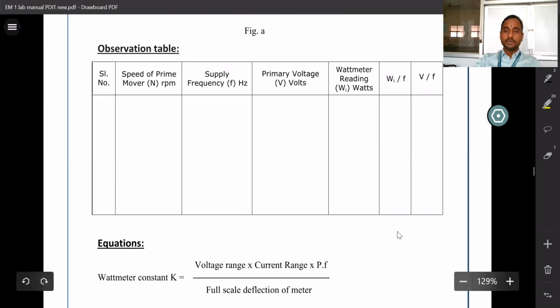So in the observation table, note the serial number, speed of the prime mover N in RPM, frequency in hertz, primary voltage V in volts, wattmeter reading, and wattmeter reading divided by frequency, that is called Wi by F, and voltage reading divided by frequency, that is called V by F. These are to be noted.